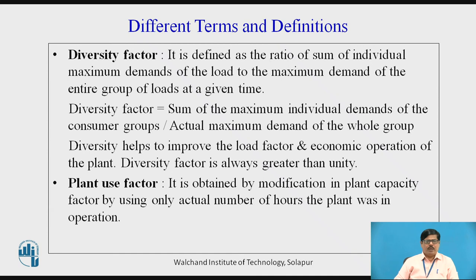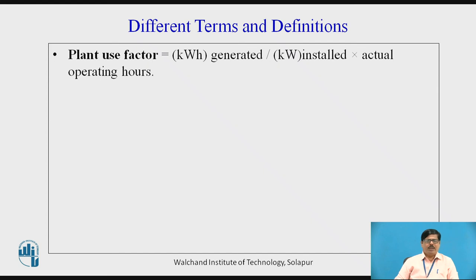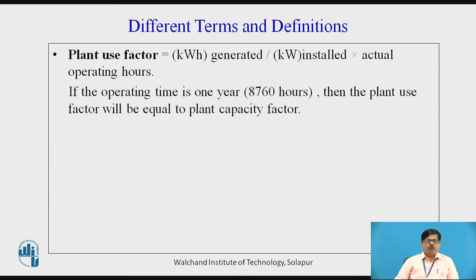The plant use factor is obtained by modifying the plant capacity factor by using only the actual number of hours the plant was in operation. It is expressed as kilowatt-hours generated divided by kilowatts installed multiplied by actual operating hours. When the operating time is one full year (8760 hours), the plant use factor equals the plant capacity factor. When actual operating hours are used instead of total hours, we call it the plant use factor rather than the plant factor or capacity factor.